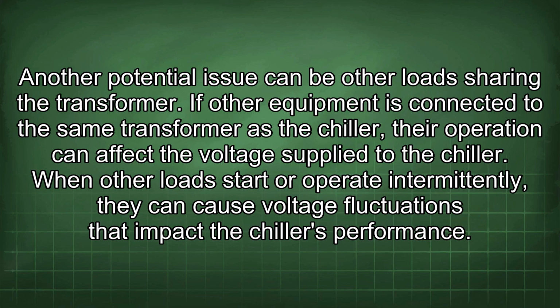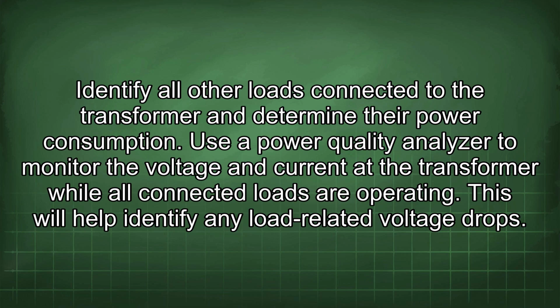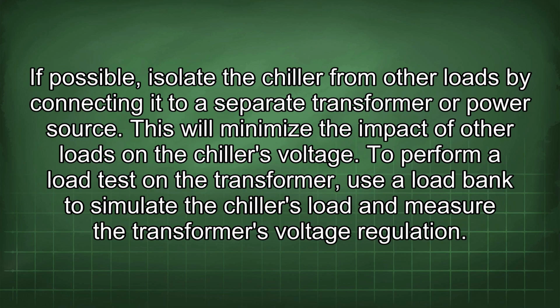Another potential issue can be other loads sharing the transformer. If other equipment is connected to the same transformer as the chiller, their operation can affect the voltage supply to the chiller. When other loads start or operate intermittently, they can cause voltage fluctuations that impact the chiller's performance. Identify all other loads connected to the transformer and determine their power consumption. Use a power quality analyzer to monitor the voltage and current at the transformer while all connected loads are operating. This will help identify any load-related voltage drops. If possible, isolate the chiller from other loads by connecting it to a separate transformer or power source. This will minimize the impact of other loads on the chiller's voltage.